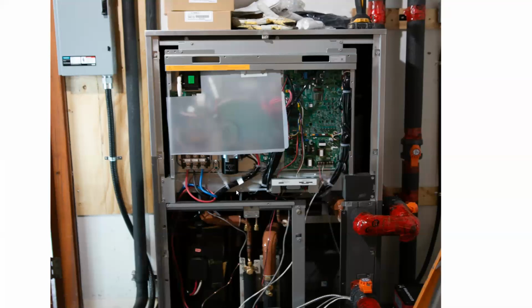One of the things introduced to us was what we call ERVs, energy recovery ventilators. We ended up having five of these installed, which constantly bring fresh air into the building. At the same time they extract the old air, they recover either the heat or the cool that's already in the air. About 60 to 80% of that energy is recycled back into the building. It's a very efficient way of bringing air in, and it reduces your costs dramatically because you don't have to bring the air up from zero temperature when drawing it in from outside, raw cold or warm air. So that was a big note.